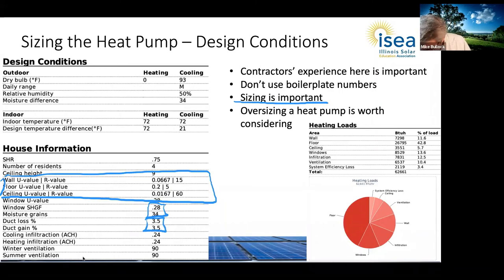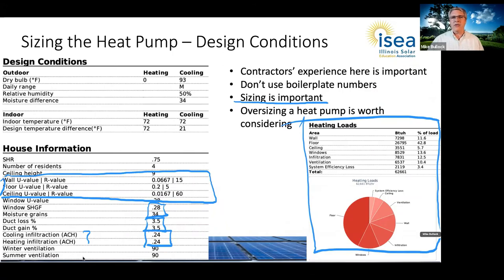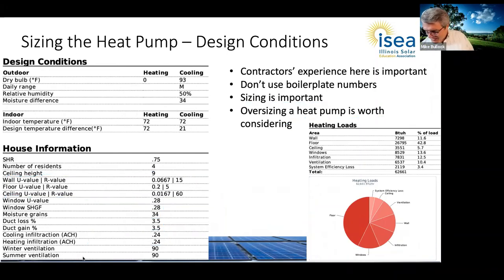This information here, the infiltration, shows how well your house is sealed. The blower door test will tell you that. I had all that information and gave it to them, so they could give me a better idea of the real heating loads, and then tell me the system that's right for me. They gave me that system, and I said okay, great. On the furnace, I'm fine with the sizing, but on the heat pump, I want to oversize it.